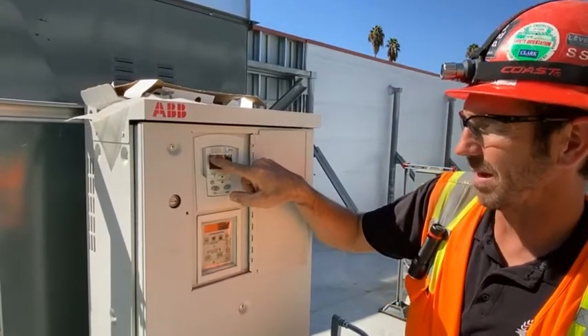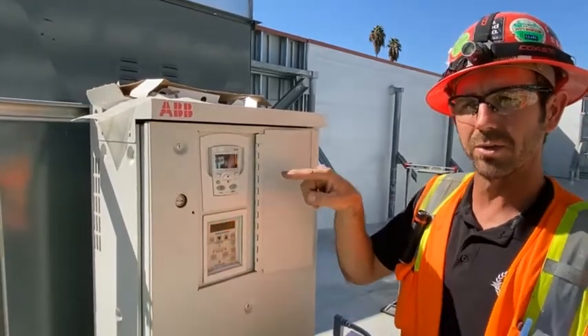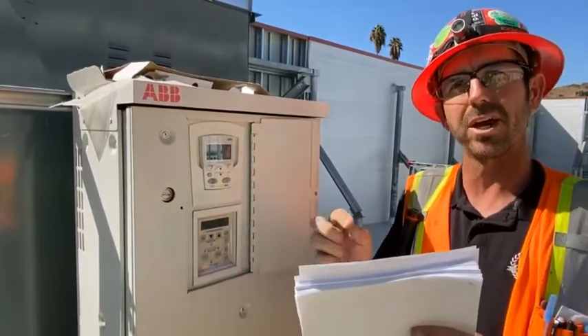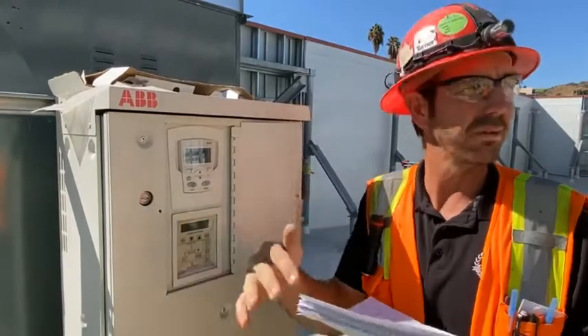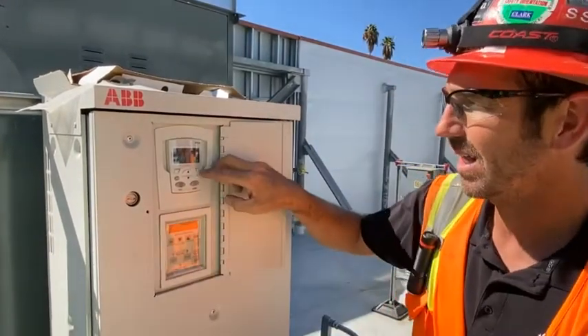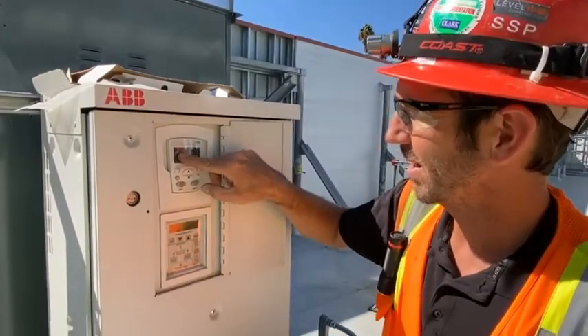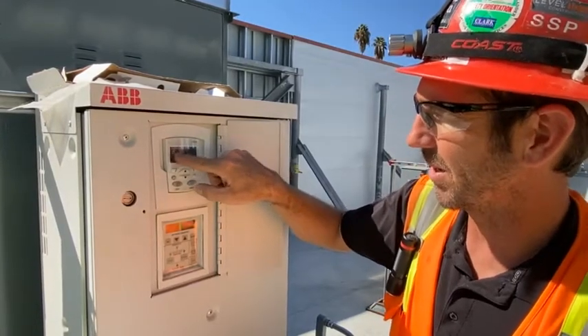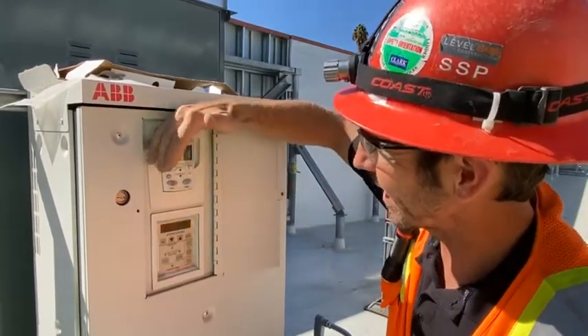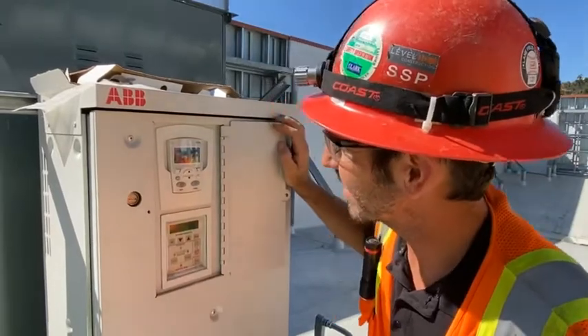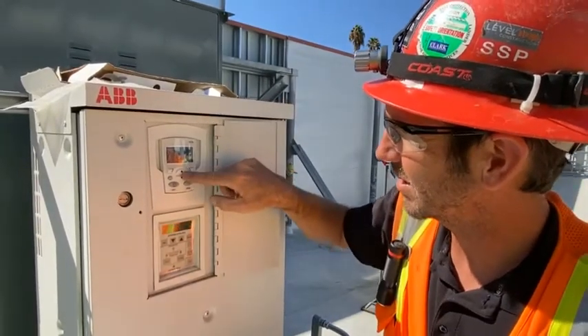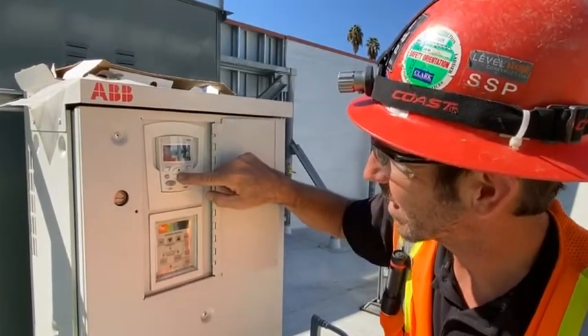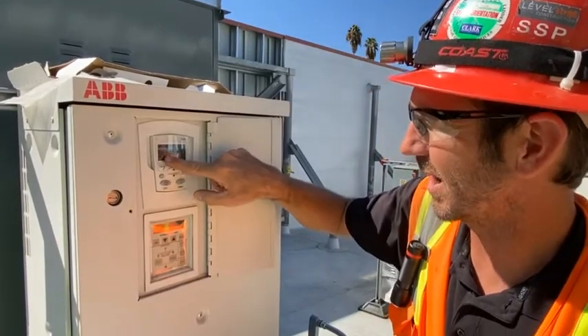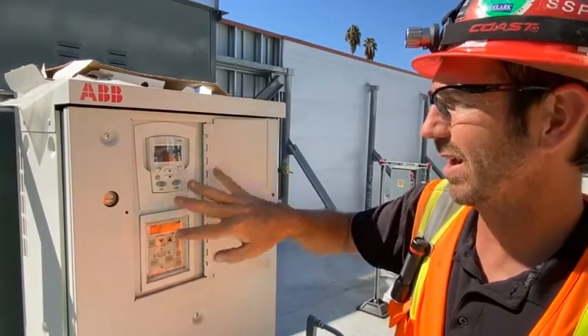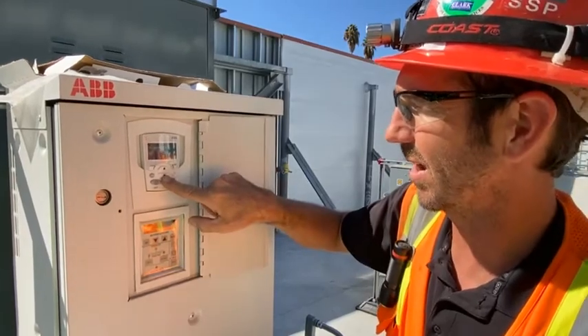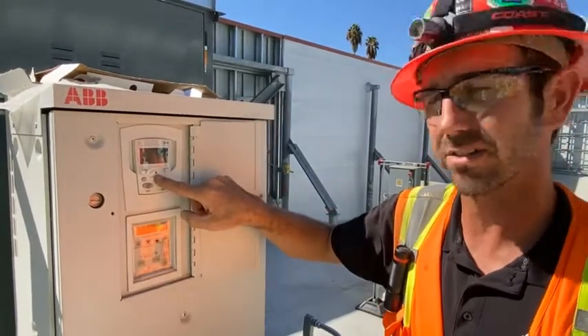And there's different sub-menus at the beginning. It'll be like an 01, and when you click into 01, you'll see a sub-menu like a 01-01 or something like that. It'll be a sub-menu that you go down. All this has already been programmed. If you ever wanted to see the speed of the motor, you could use the 01, it's operating data. The 03 is setting up fault signals. In 04, you can see fault history. The start, stop, all that, none of that stuff should need to be changed. We're just using the factory start, stop setting on here.